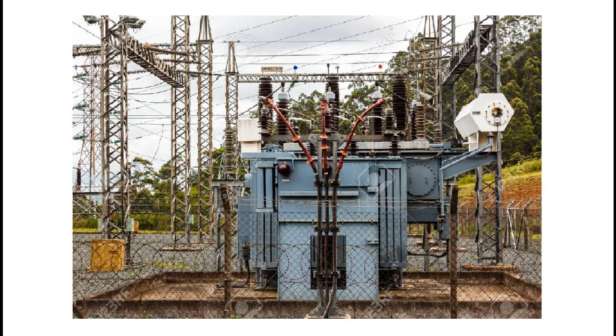Producing an earth grid within a substation is a different topic that needs an explanation of how earth pits are created. For the time being, we will consider that an earth point is available near the equipment of the substation. On the other hand, the equipment of the substation has an earth pad to be connected to that nearer earth point. Towers and plinths are concrete foundations made to provide firm support to equipment, but their foundation bolts or bars are not produced to give good earth contact with minimum electrical resistance. Therefore, a separate earth point is connected with the earth pad of the equipment.